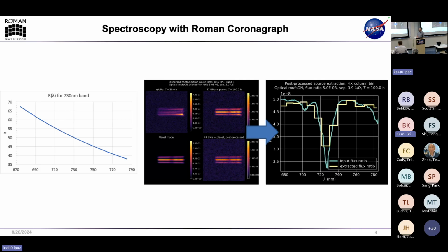For spectroscopy specifically, our science case is what drove the resolution and band passes that we're talking about here. You can see that nonlinear dispersion curve on the left, where just because we're in a zero deviation configuration, we couldn't flatten the spectral response particularly well. So this is the best we did, and we tweaked it. You can think of that as an advantage or a disadvantage, knowing in context that this can work in any of the 4 bands, by the way. What this means is you could use the band 3 prism in band 2 for a higher resolution, or conversely, you could use band 2 and band 3 if you wanted a lower resolution and needed to boost your SNR. So just a note for people who are going to be using this in the future.